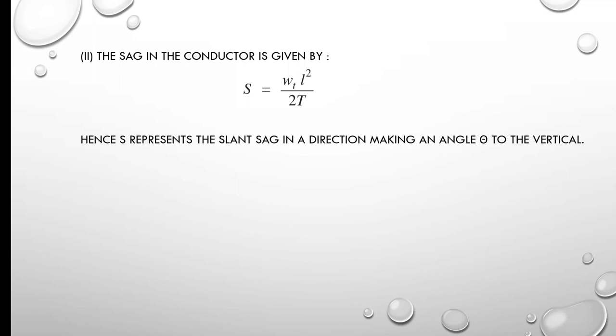With this formula, we can calculate the sag in the conductor: S = WtL²/2T. Here S represents the slant sag in a direction making an angle θ to the vertical. The vertical sag is S cos θ.